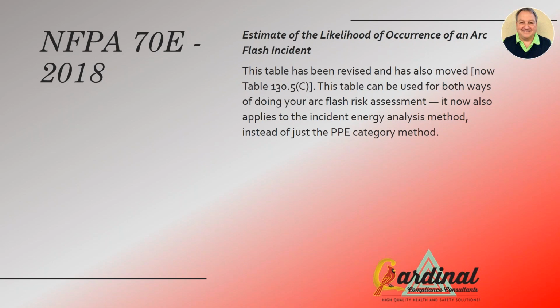Also, we need to take a look at arc flash. We're learning more about the studies of arc flash, their hazards, and their effect on the human body. These were some charts and graphs located in the back of the book, but now we're moving towards calculating the arc flash current at each device and picking the proper gear for protection based on your on-site, specific calculation.